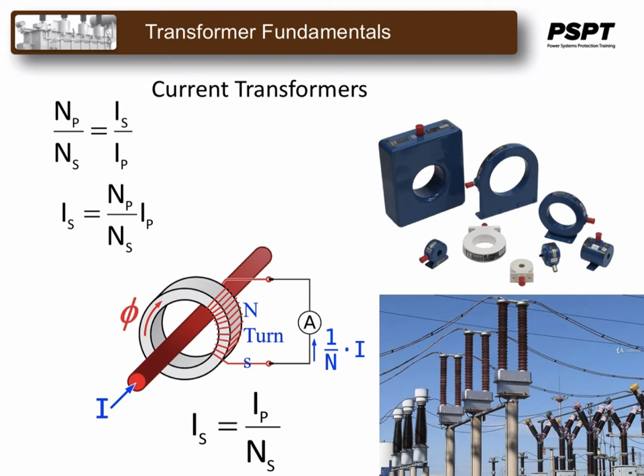If the primary is 1, or it's a bushing or a bus bar going through the donut CT, then the secondary current is equal to the primary current divided by the number of turns of the secondary.